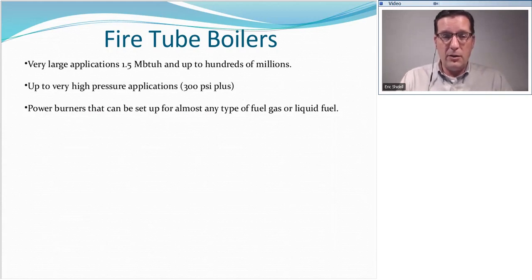They are going to be used in low pressure applications and/or in very high pressure applications, up to 300 PSI water. Now, very high pressure applications are going to be used in things like high-rise buildings, district heating systems, campuses, entire downtown areas, and they're very dangerous. So your average HVAC heating commercial residential technician needs to stay away from high pressure systems.